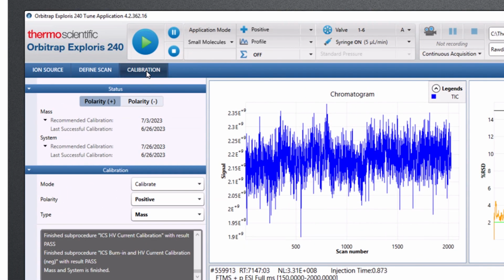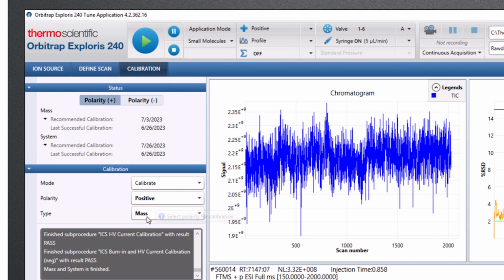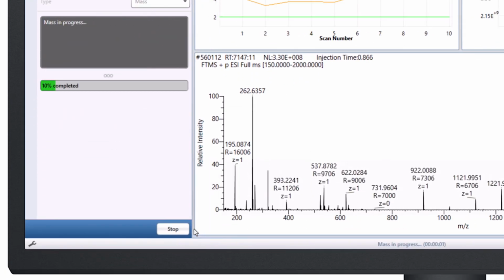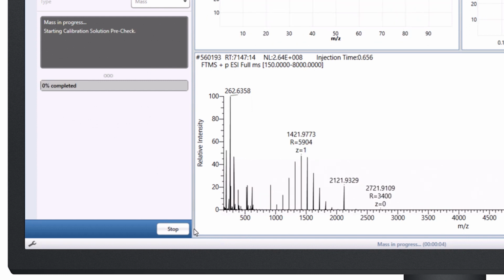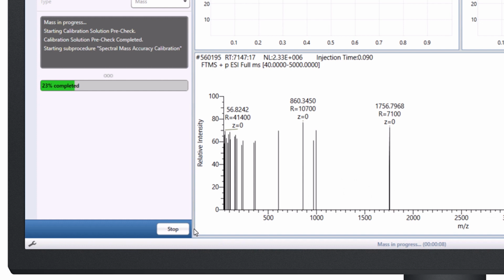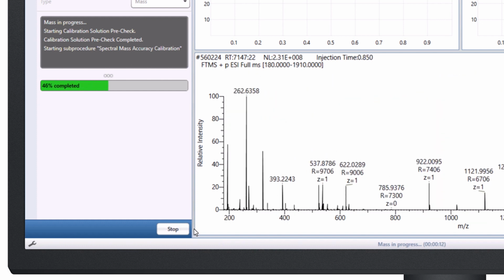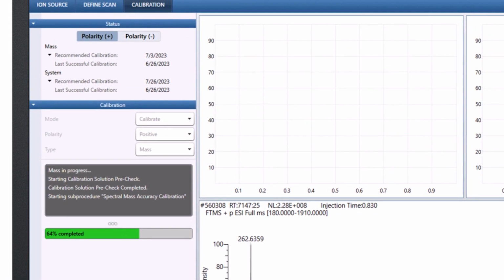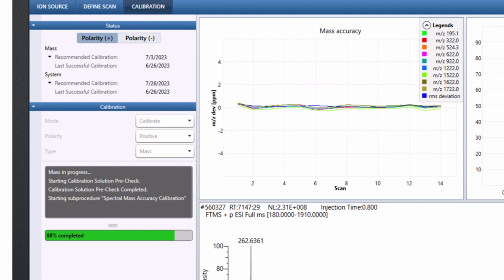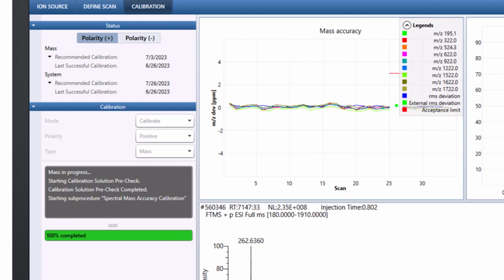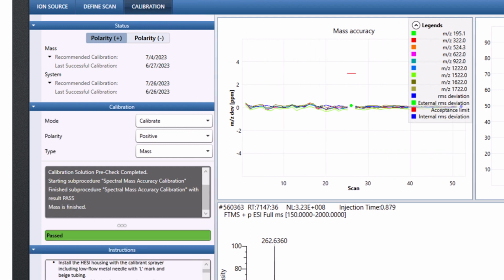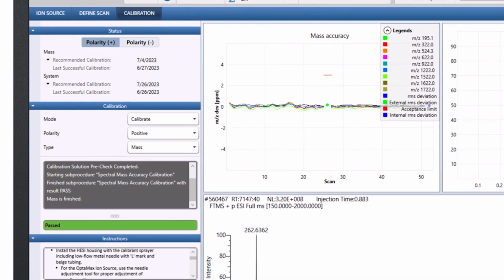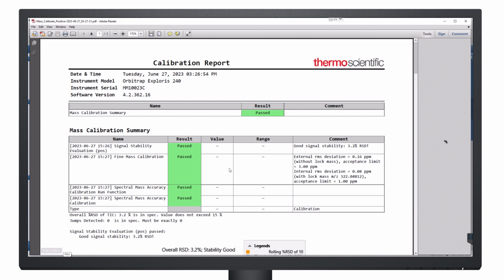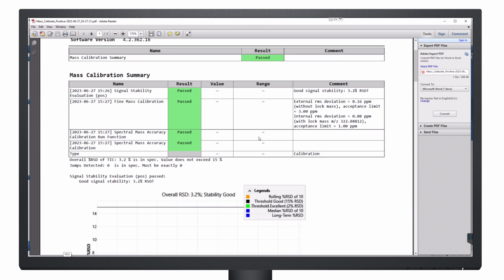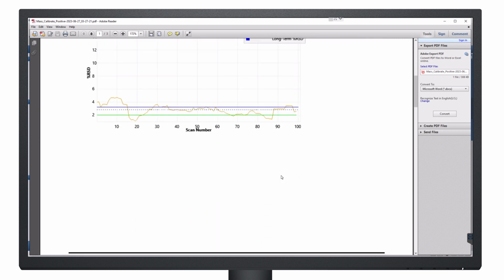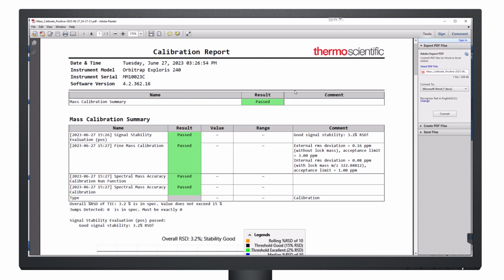Go over to the calibration tab, make sure that I have calibrate, positive, and mass, and then go ahead and click start to initiate that calibration sequence. You'll notice at the start it does check our spray stability, so that was a good reason why to check that ahead of time. Let the program go ahead and run through, and it's a pretty quick calibration here. We're already nicely tight, right around 0 ppm deviation, slightly deviated on the mass accuracy, and then we passed. So that is a simple, pretty straightforward operation. And the next step is we're getting a nice report out showing what the calibration looked like. So that's a nice file for your keeping. And that's it. That's how you would calibrate your instrument.